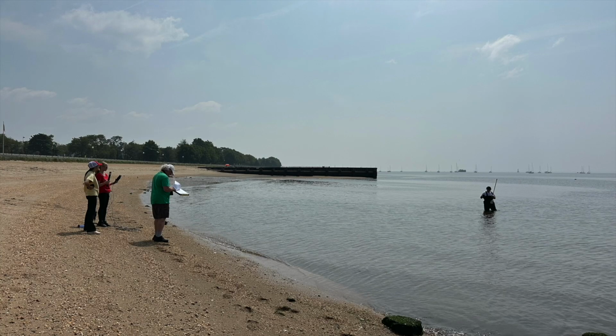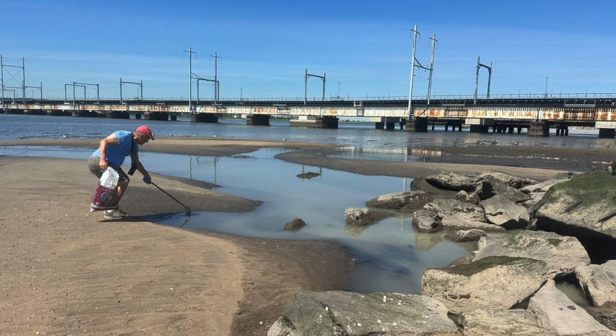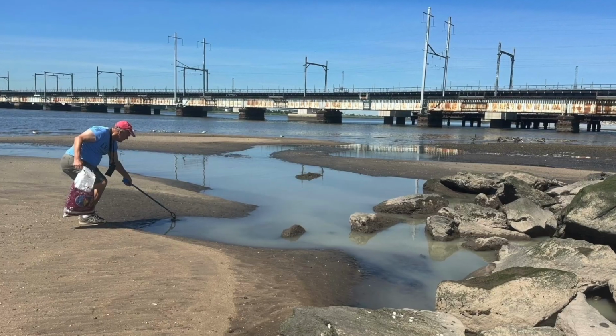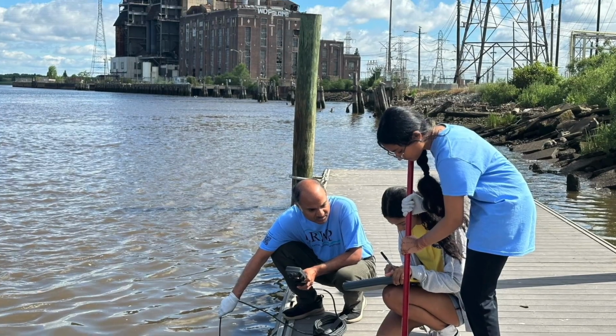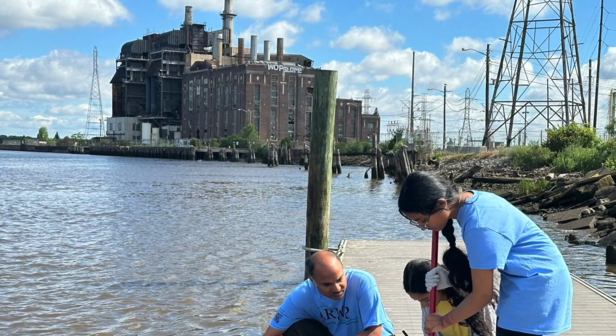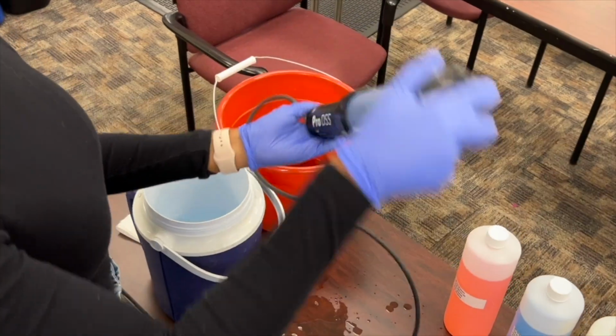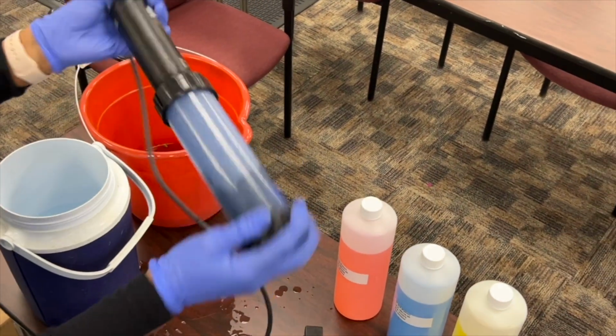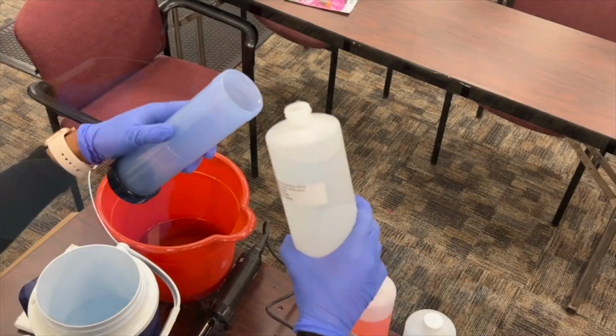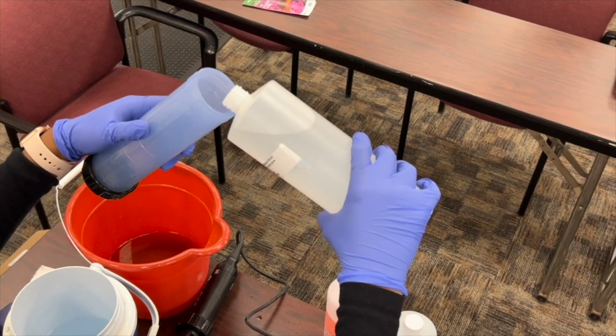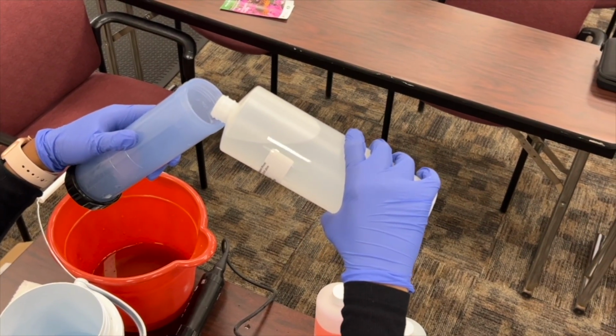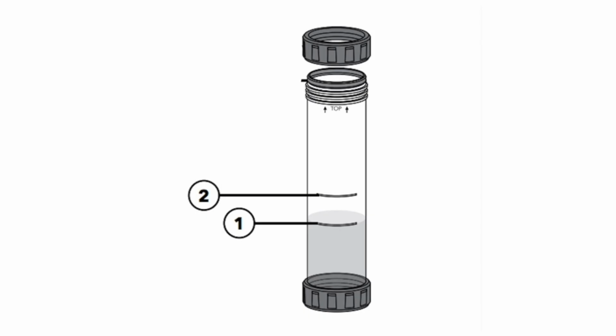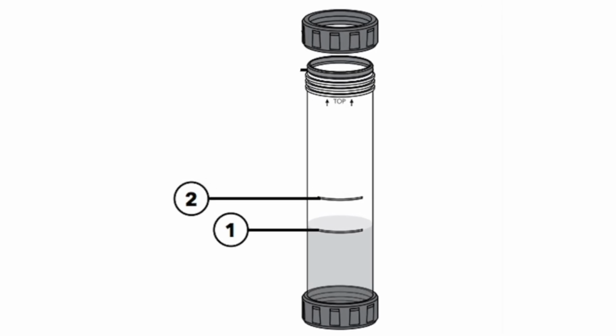Since the waters of the New York, New Jersey harbor estuary are tidally influenced, we do expect higher salinity readings that vary with the tides. However, saline water can also be the result of industrial discharges or road salts. Always make sure you rinse the sensors and calibration cup after using any buffers. After rinsing, tilt the calibration cup at an angle and slowly pour the conductivity standard up to the second line to prevent bubbles.